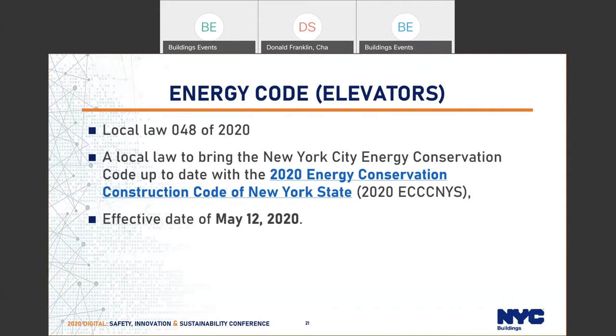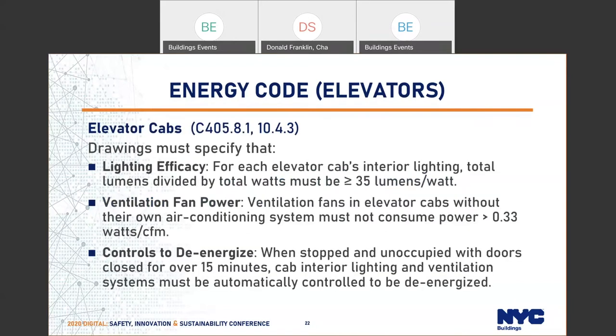The energy code was passed by Local Law 48 of 2020, effective May 12, 2020. This local law brings the New York City Energy Conservation Code up to date with the 2020 Energy Conservation Construction Code of New York State. It has impact on elevators and escalators: lighting inside the cab must meet certain efficiency requirements — brightness divided by total watts must be greater than or equal to 35. For fan ventilation, power should not consume more than 0.33 watts per cubic feet per minute of ventilation. There is also a requirement for cab lighting to turn off after no use.